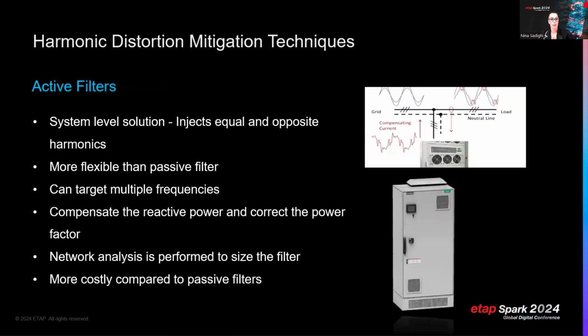Active filters are other solutions. These are system-level solutions that inject equal and opposite harmonics. They're much more flexible and target multiple frequencies. They compensate reactive power and correct power factor as well. The downside of that is these are expensive and they do need a larger footprint.